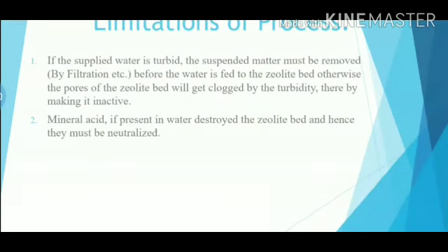Now, the limitations. If the supplied water is turbid, the suspended matter must be removed before the water is fed to the zeolite bed. Otherwise, the pores of the zeolite bed will be clogged by the turbidity, thereby making it inactive. Now, if mineral acid is present in water, it destroys the zeolite bed and hence, they must be neutralized.